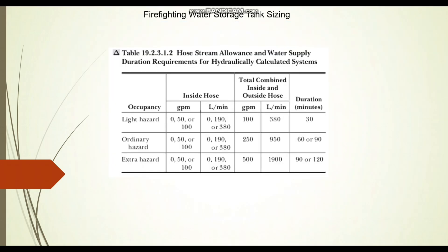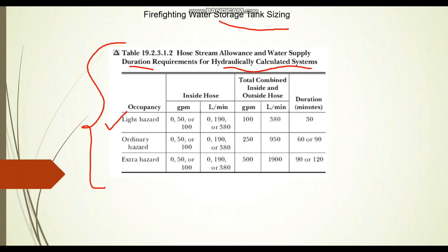Now we are going to find out the storage tank sizing for the firefighting system. This table is taken from NFPA 13, showing the hose allowance and water supply duration requirements for hydraulically calculated systems. Different hazard levels are given: light hazard, ordinary hazard, and extra hazard. The required storage duration is 30 minutes for light hazard, 60 to 90 minutes for ordinary hazard, and 90 to 120 minutes for extra hazard.